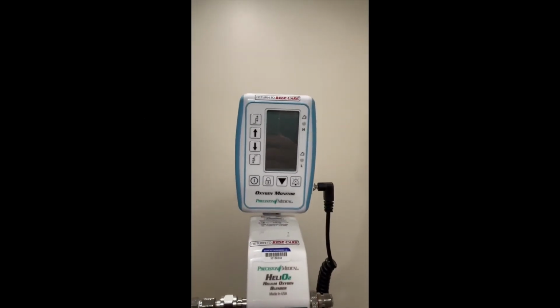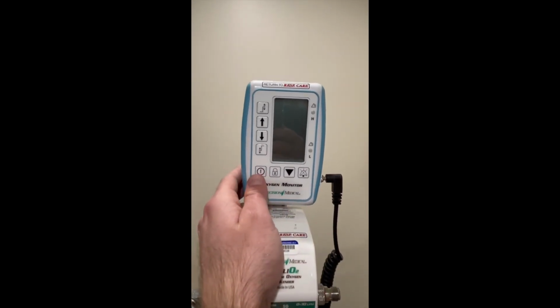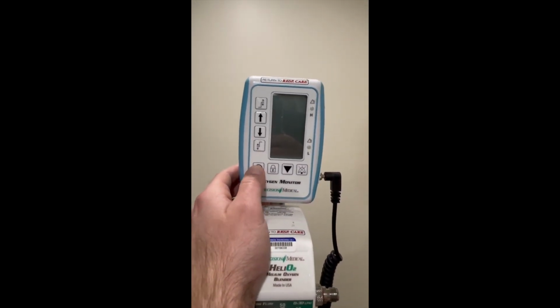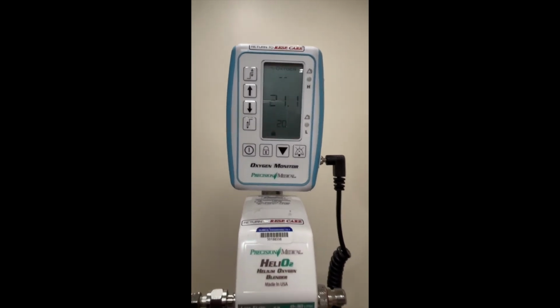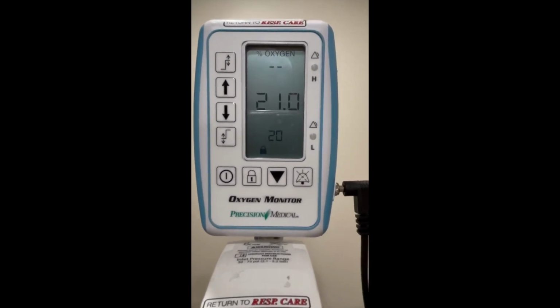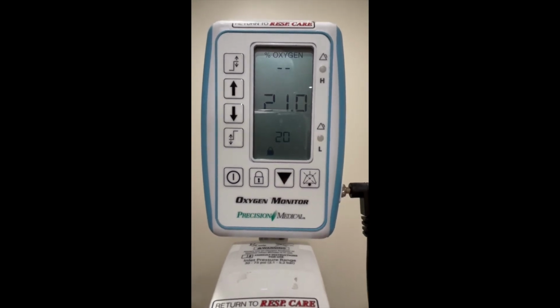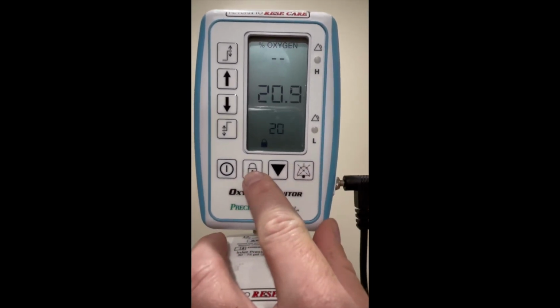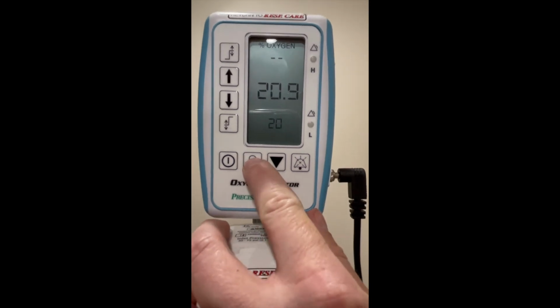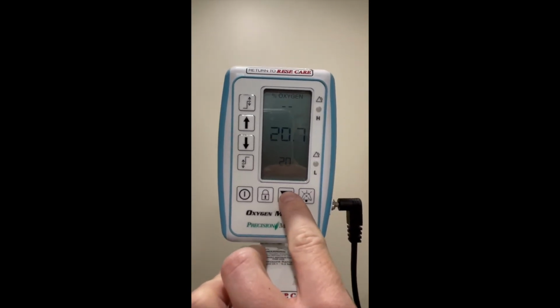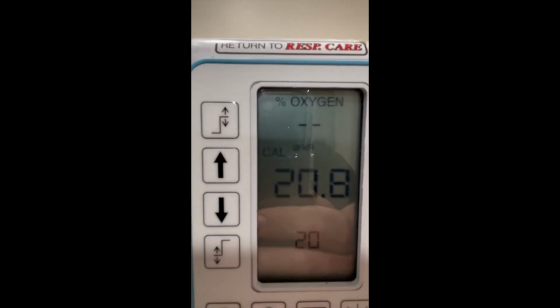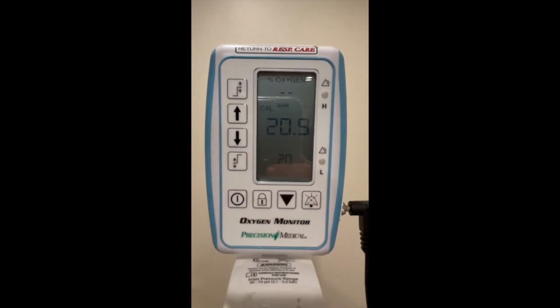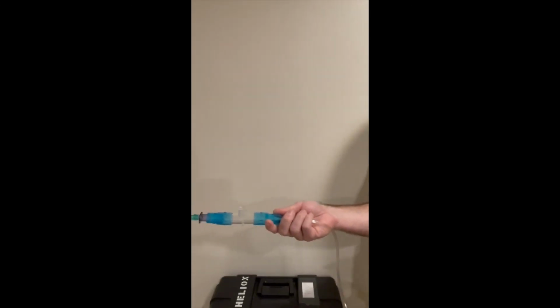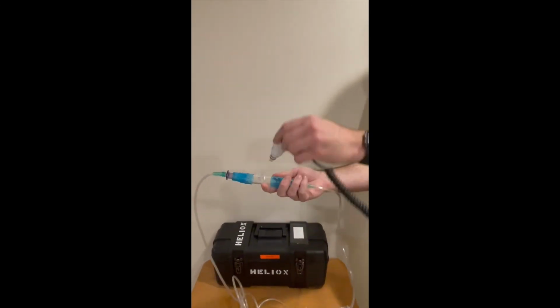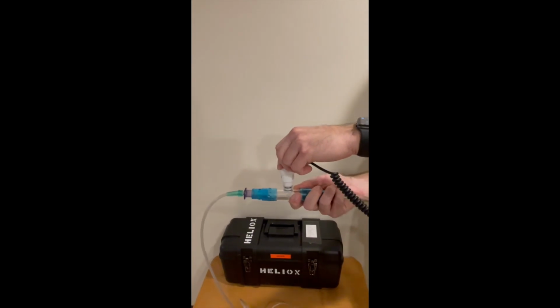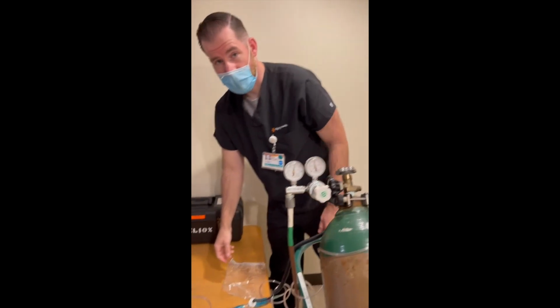We're almost ready to administer Heliox. We want to first turn on our oxygen sensor. It's very important that before we start this, we calibrate it. We go through calibration first by pressing the lock button to unlock, and then the down arrow to go through calibration. It will automatically calibrate. After calibration has been performed, you can place the probe into the T-piece. Now we're ready to administer the Heliox.